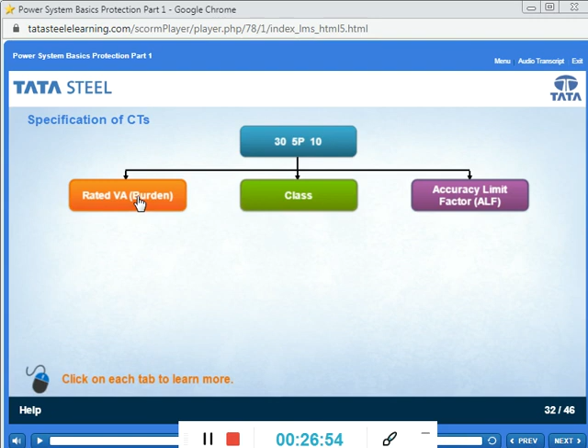Rated burden: value of burden in VA on which accuracy claims are based. Preferred values: 2.5, 5, 7.5, 10, 15, 30 VA. ZB, the rated burden in ohms, is equal to rated VA divided by IN squared.